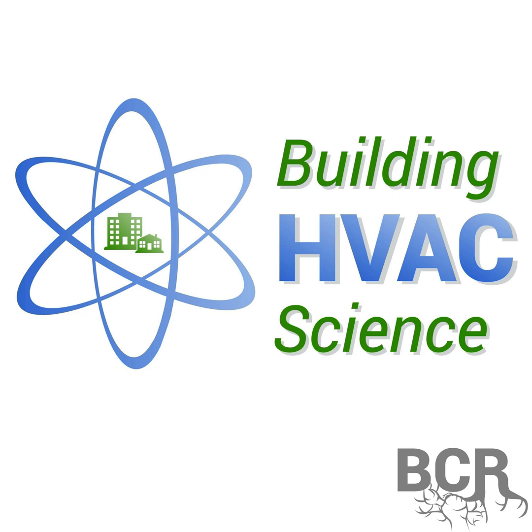Yes, and that's an important point. So the serve has built into it standard filters. So they're not a custom filter. They're a standard 10 by 20 size filter, and you can put in 1-inch or 2-inch size filters, as well as, depending on someone's sensitivity to pollens and other allergens, you can put in the MERV rating or Filtrete rating that you'd like, as well as in some areas where forest fires and smoke outdoors, putting in like a carbon impregnated filter.